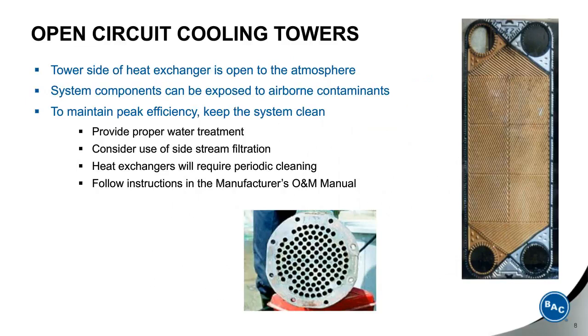Now, the tower side of the heat exchanger is open to the atmosphere. This means that system components can be exposed to airborne contaminants. Now, these contaminants can include dust, dirt, pollen, boiler exhaust, and the like. So to maintain peak efficiency, you must keep the system clean. And that can be done through a proper water treatment program.